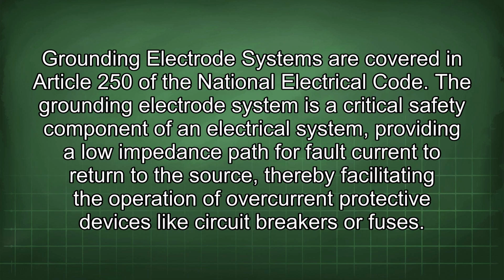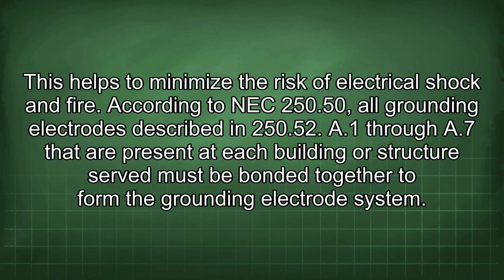Grounding electrode systems are covered in Article 250 of the National Electrical Code. The grounding electrode system is a critical safety component of an electrical system, providing a low impedance path for fault current to return to the source, thereby facilitating the operation of overcurrent protective devices like circuit breakers or fuses. This helps to minimize the risk of electrical shock and fire.